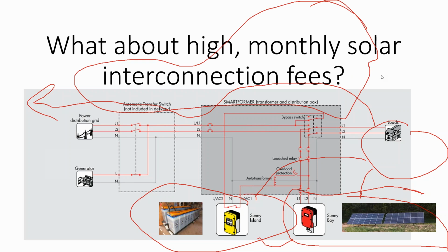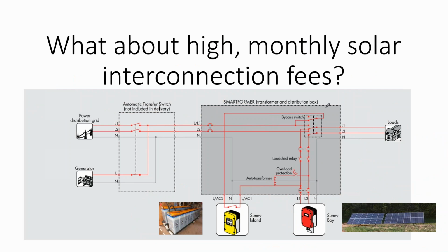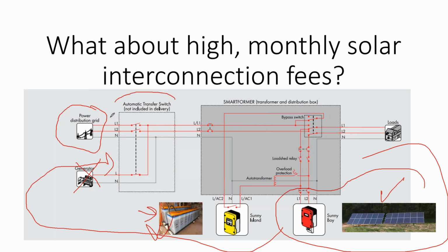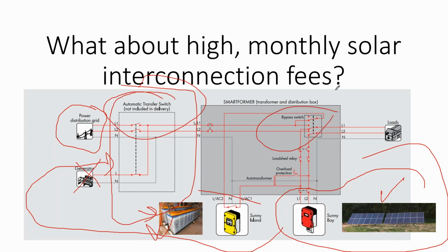So you might ask: is it possible to disconnect my home during the day and reconnect at night, so my solar array isn't outflowing onto the grid and isn't connected to the grid at all? And the answer is yes. Under that circumstance, we'd get rid of the generator here and say the grid is essentially our generator — if our batteries get low, we'll charge them back up with the grid if we don't have a solar array. You take the solar array and land it on the other side of the transfer switch, and the transfer switch will switch fast enough not to interrupt power in your electric service panel.